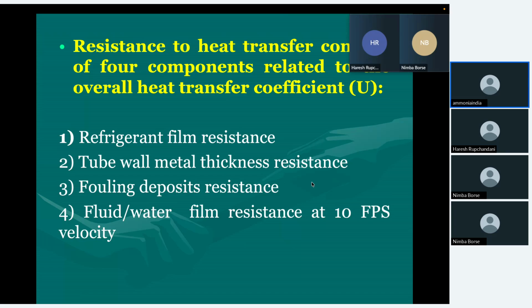Now, when we calculate UA delta T, what does U mean? U is 1 upon the resistance to the heat transfer. Resistance to heat transfer consists of 4 components related to the overall heat transfer coefficient. That is refrigerant side film resistance, tube wall metal thickness resistance, fouling deposits resistance, and water film resistance, assuming a 10 feet per second velocity. So water film causes resistance, fouling deposits cause resistance, and of course refrigerant film. The reciprocal of the addition of all these resistances will give you the U value.